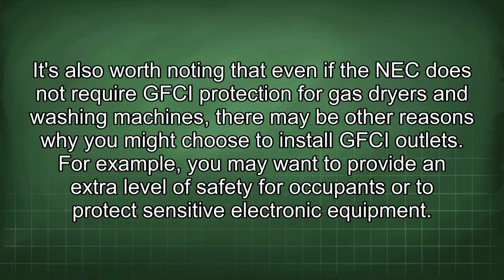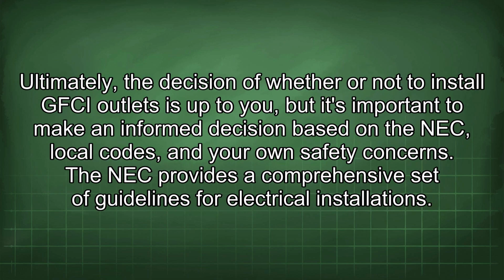It's also worth noting that even if the NEC does not require GFCI protection for gas dryers and washing machines, there may be other reasons why you might choose to install GFCI outlets. For example, you may want to provide an extra level of safety for occupants or to protect sensitive electronic equipment. Ultimately, the decision of whether or not to install GFCI outlets is up to you, but it's important to make an informed decision based on the NEC, local codes, and your own safety concerns.